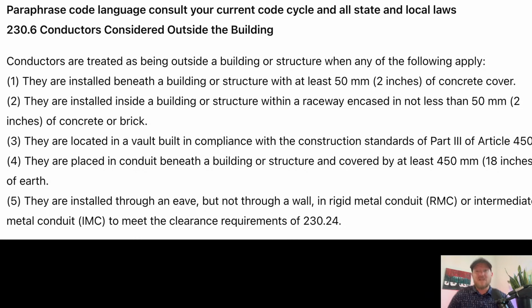Conductors are treated as being outside of a building or structure when any of the following apply: they are installed beneath a building or structure with at least 2 inches of concrete cover; they are installed inside a building or structure within a raceway encased in not less than 2 inches of concrete or brick; they are located in a vault built in compliance with the construction standards of Part III of Article 450; they are placed in a conduit beneath a building or structure and covered by at least 18 inches of earth; or they are installed through an eave, but not through a wall, in rigid metal conduit or intermediate metal conduit, meeting the requirements of 230.24.